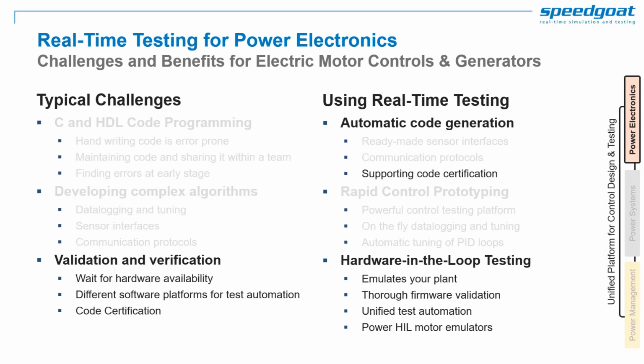Finally, it is possible to emulate your plant using hardware-in-the-loop testing. You can not only start testing before your power converter is available, but you can also test your virtual plant in extreme conditions without risking the real motor inverters, or even use Power Hardware-in-the-Loop to test actual motor inverters with virtual motors using power interfaces from a few watts to megawatts.